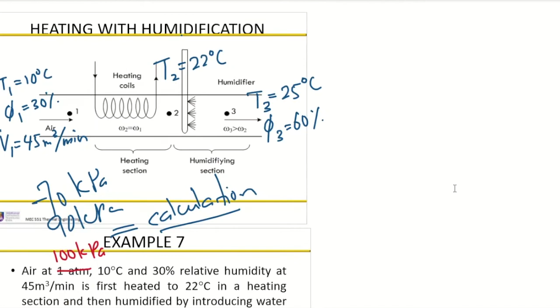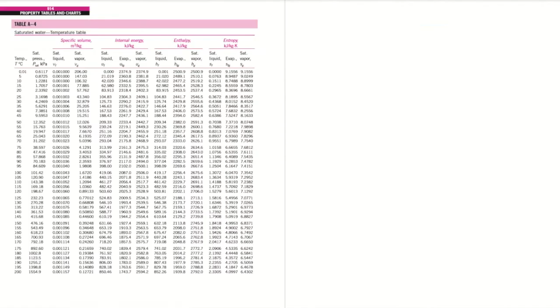We need to calculate Q dot in, which equals m dot A times (h2 minus h1). So first, we need to determine the partial pressure of water vapor, PV1, which is based on relative humidity multiplied by the saturation pressure, P saturation. For our case, it's at 10 degrees C. So this is going to equal 0.3 multiplied with, so now we need to take a look at the property table at 10 degrees C.